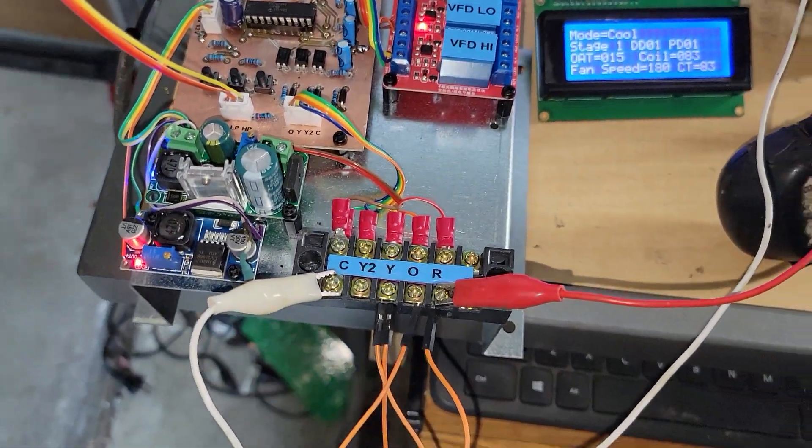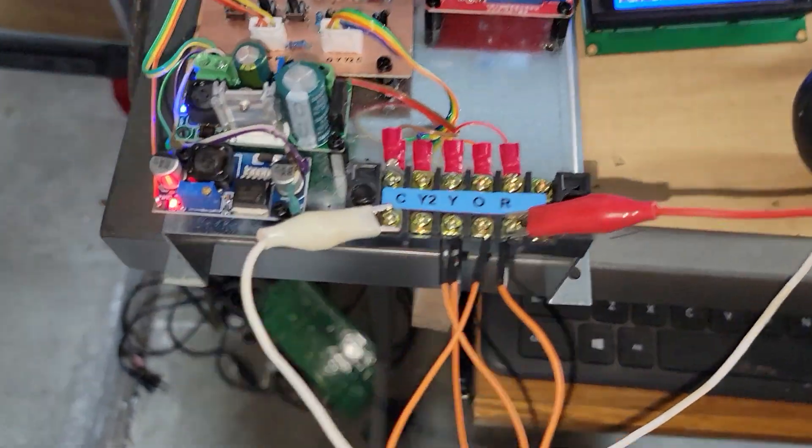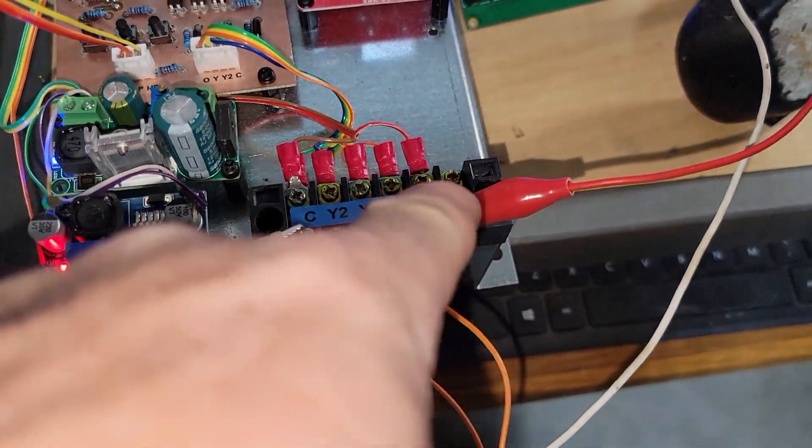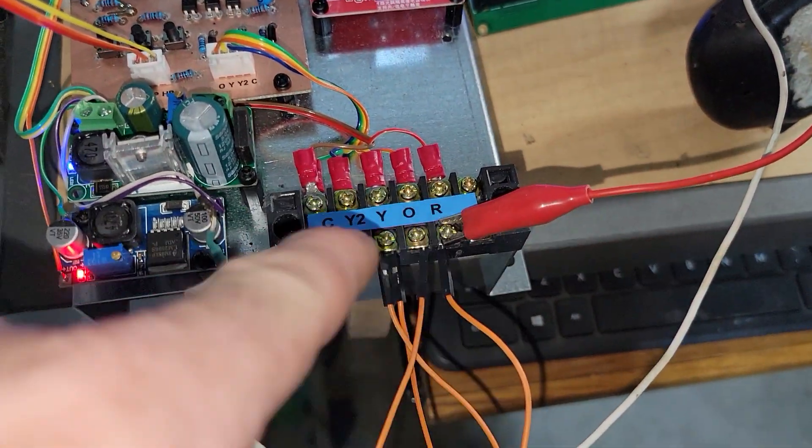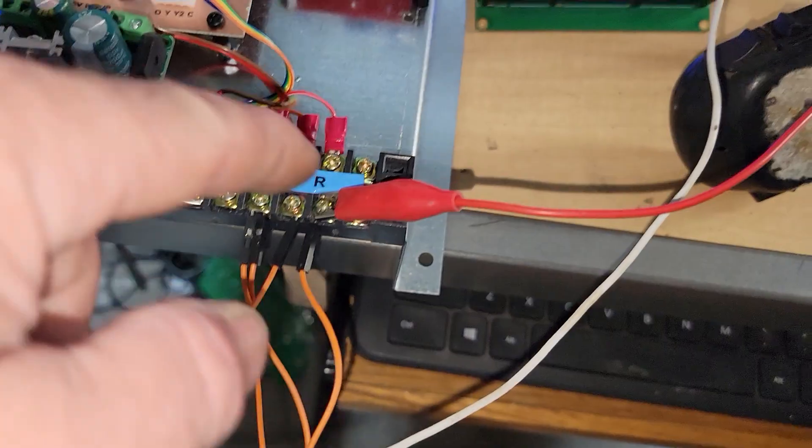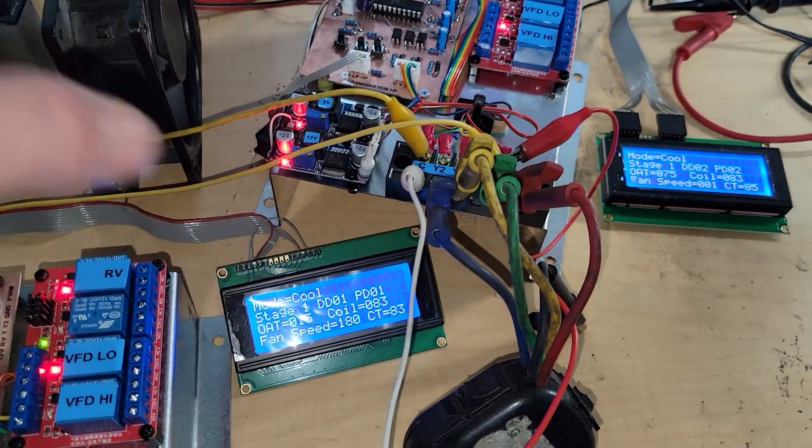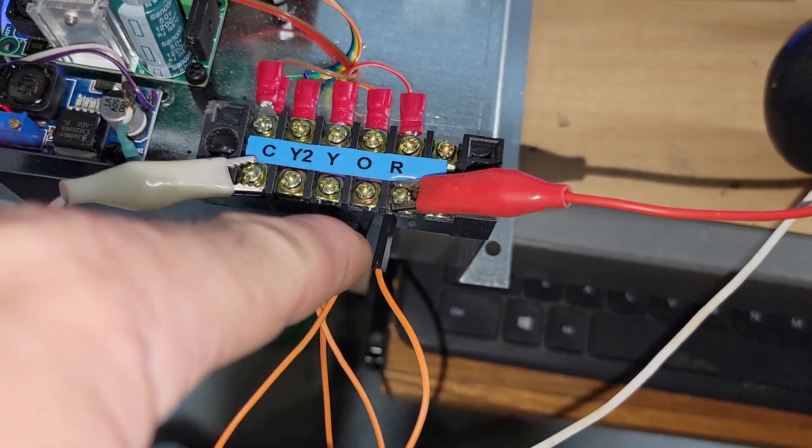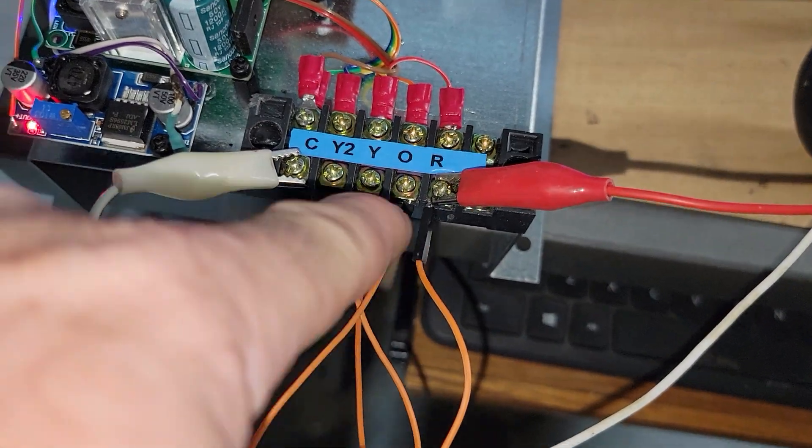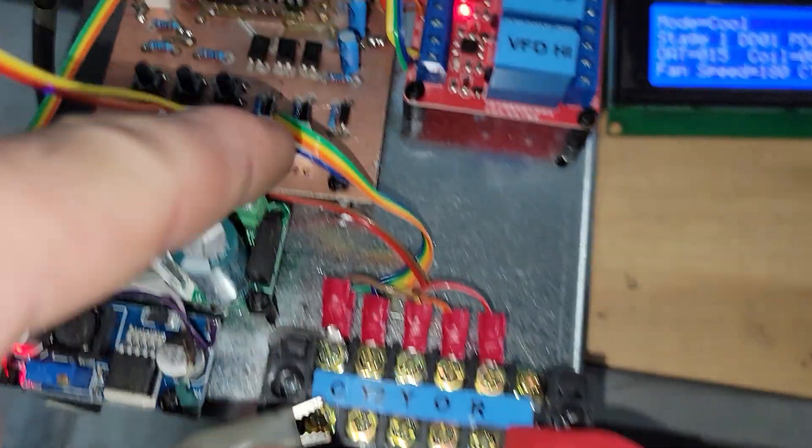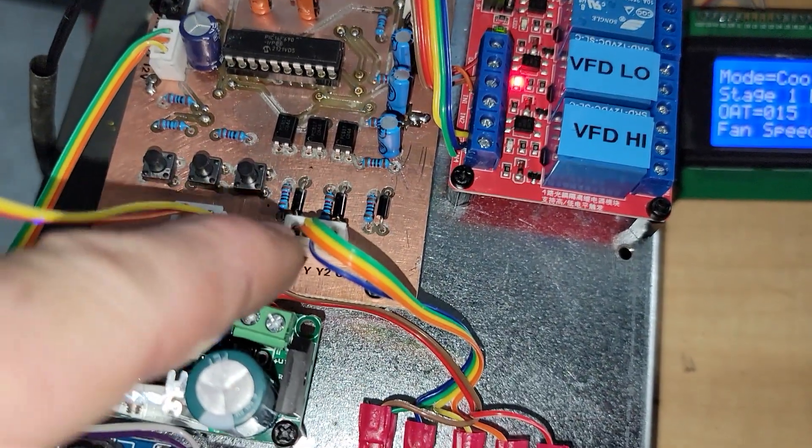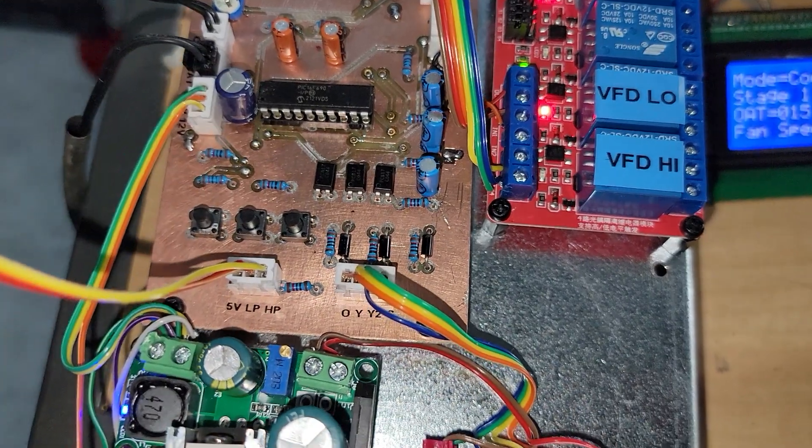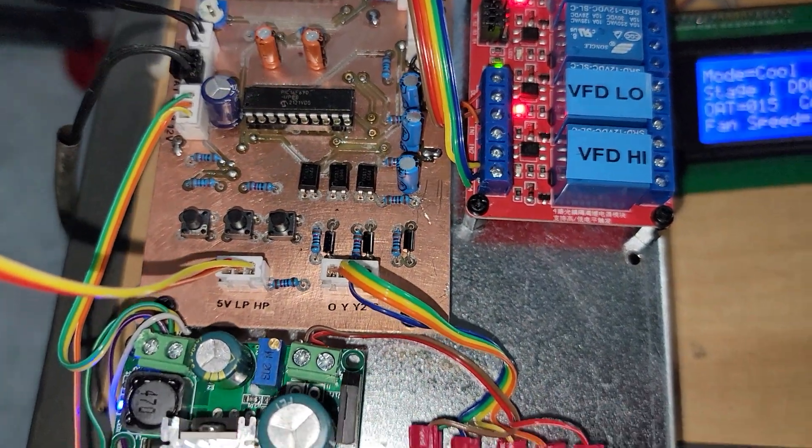The way I have this is - this is my 24 volt thermostat strip. I just have common and red coming from, sharing the same transformer as that one for right now for testing. I just have first stage with the reversing valve connected. They go in through the rectifiers, optical isolators, and then into the processor.